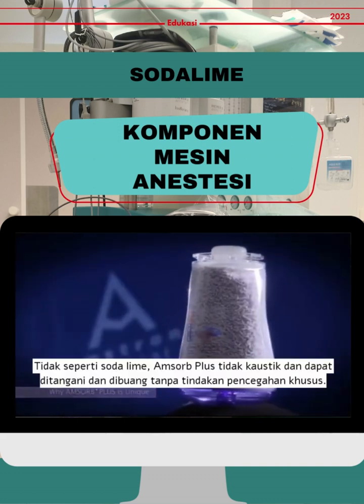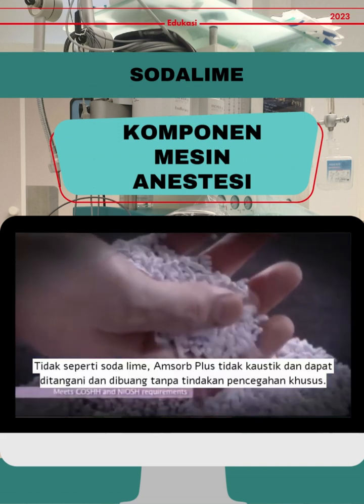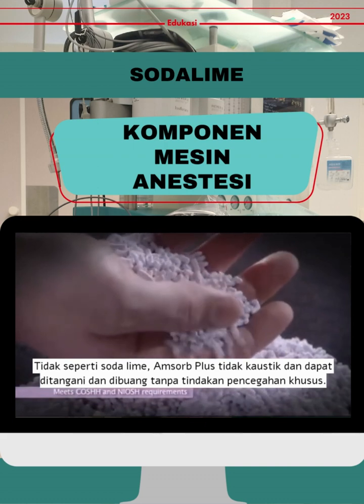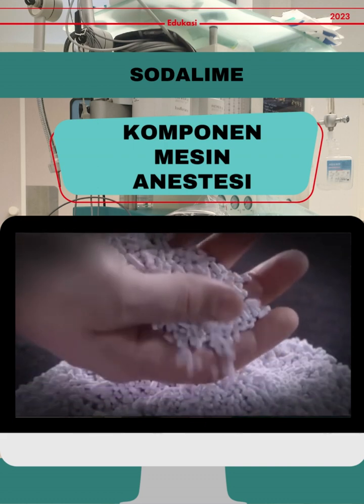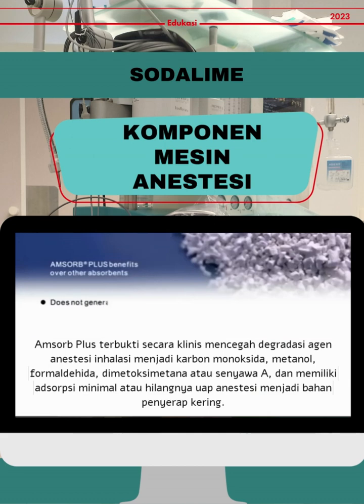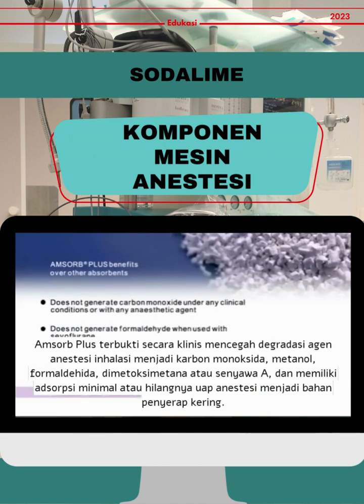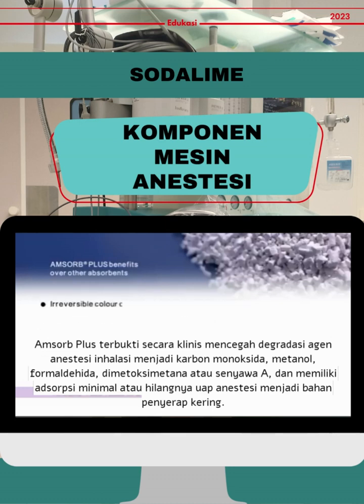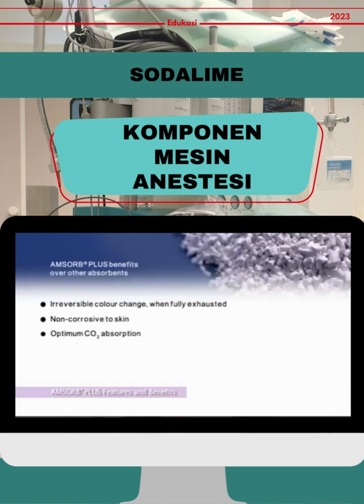Unlike sodalimes, Amsorb Plus is not caustic and can be handled and disposed without special precautions. Amsorb Plus is clinically proven to prevent degradation of inhalational anesthetic agents to carbon monoxide, methanol, formaldehyde, dimethoxymethane or compound A, and to have minimal adsorption or disappearance of the anesthetic vapor into desiccated absorbent material.